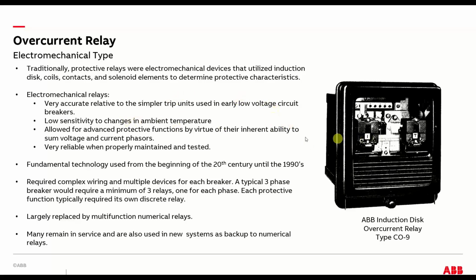The electromechanical relays are kind of clockwork-like devices, and they tended to be in the medium voltage world because they were more accurate, and there were more things you could do with them in terms of protection, as opposed to equipment at low voltage. The electromechanicals used induction disks and solenoids and things like that to achieve the protective function, whereas the circuit breaker at low voltage used thermal heaters or just thermal elements plus some magnetic stuff. But that was sort of the origins of it.